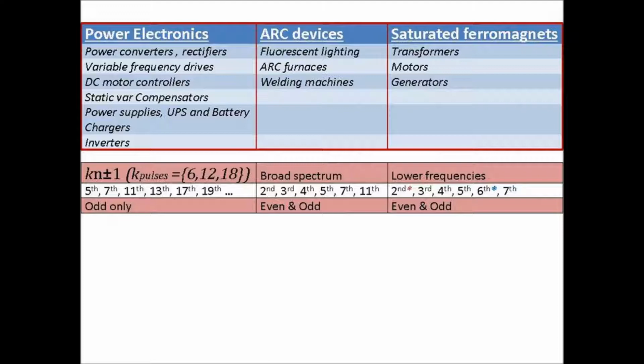Saturated ferromagnets. That was the traditional cause of harmonics in the system. Back in the day, when they were rolling out the high voltage grid, transformers were first and foremost. They introduced some harmonics onto the system. Basically, they would be operated slightly above their knee point, where they're most efficient, and you'd end up with eddy currents in your transformers, which you call the heating effect, and you'd have some harmonics through that. Motors and generators are also smaller, but they do contribute to harmonics in the same manner as transformers would do.